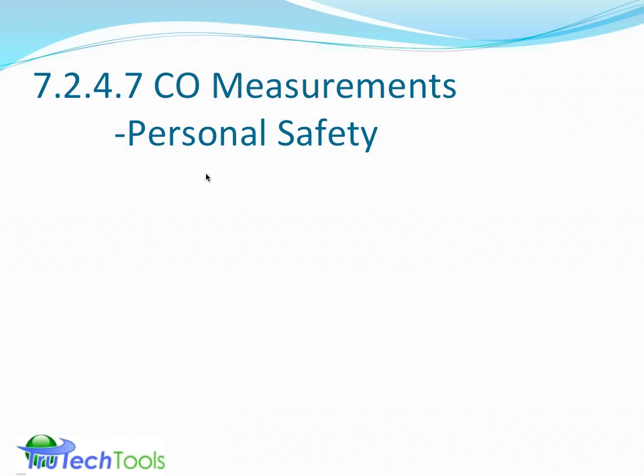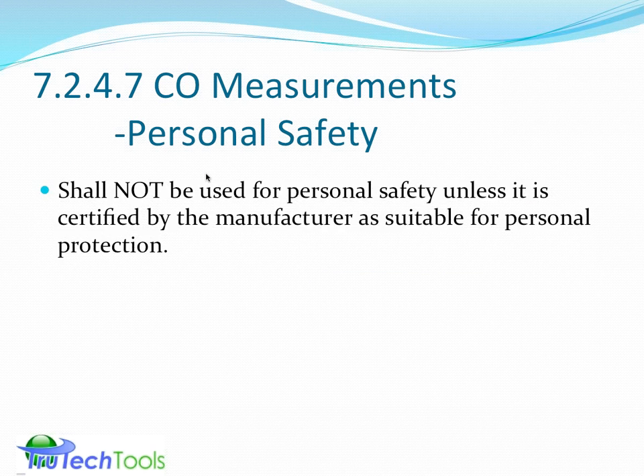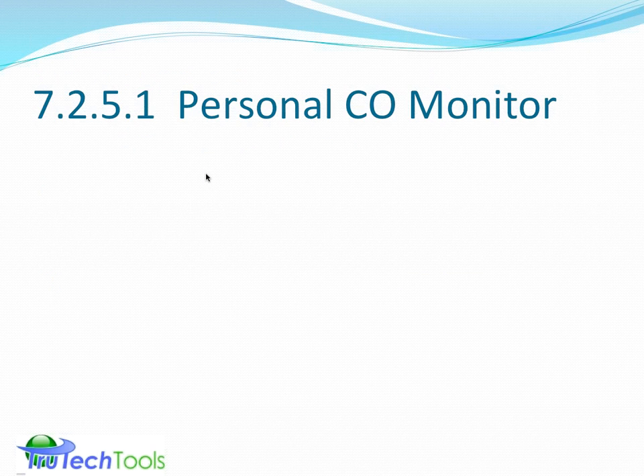There's also a line in the standard, section 7, 7.2.4.7, that talks about CO measurements from a personal safety standpoint. The standard as it exists right now says the equipment shall not be used for personal safety unless it is certified by the manufacturer as suitable for personal protection. I've never actually seen this certification myself, so I'm looking for clarification from BPI. And again, this may be one of the points where they change the standard in its draft and review phase. For this industry, you don't usually see it certified by the manufacturer.